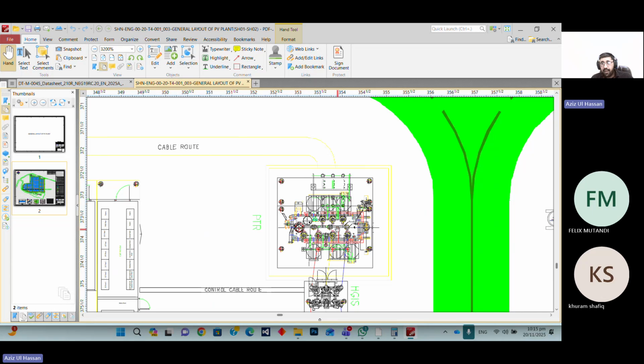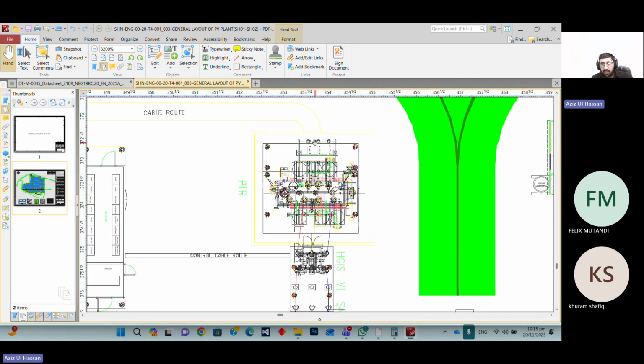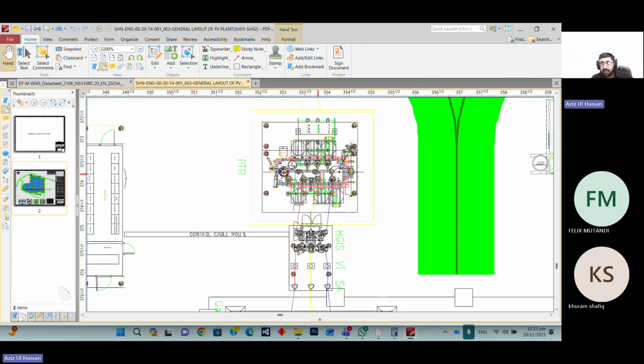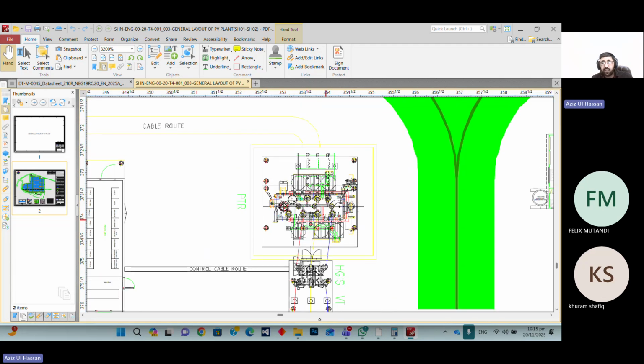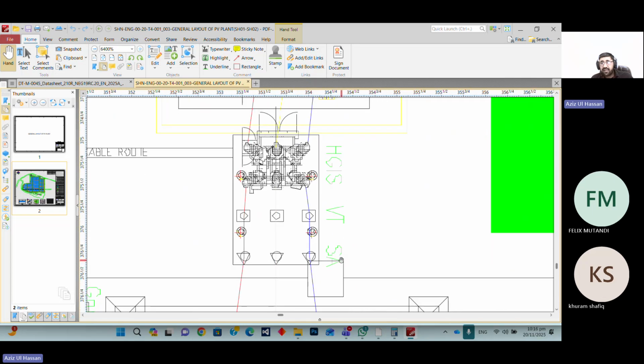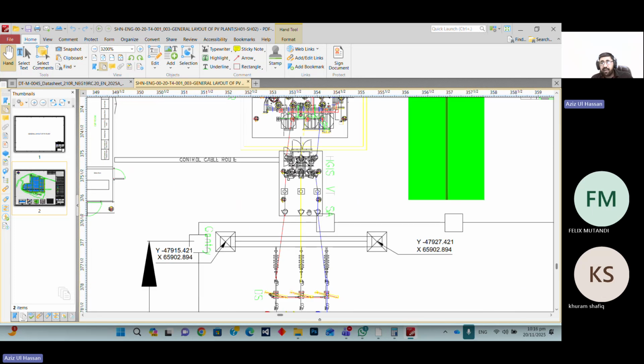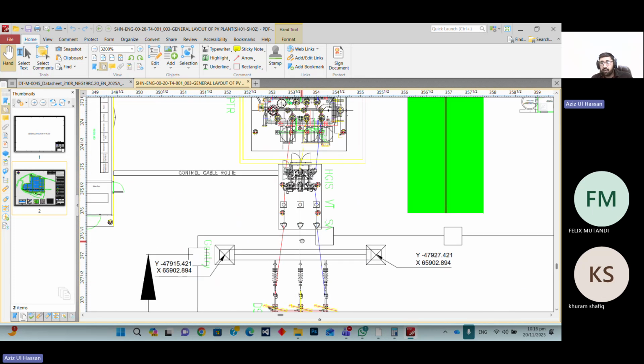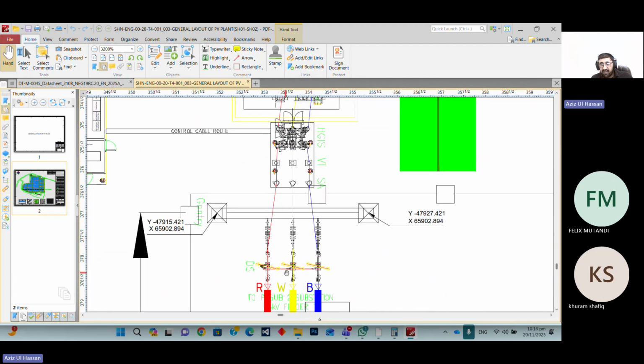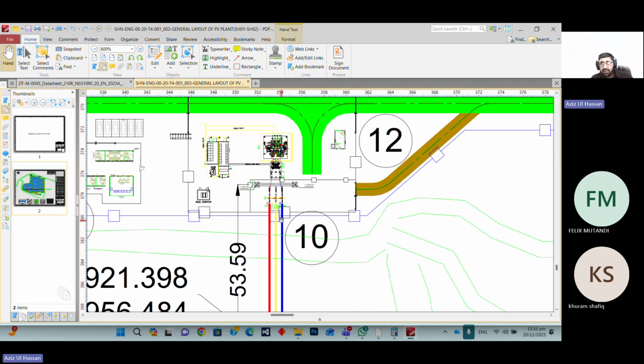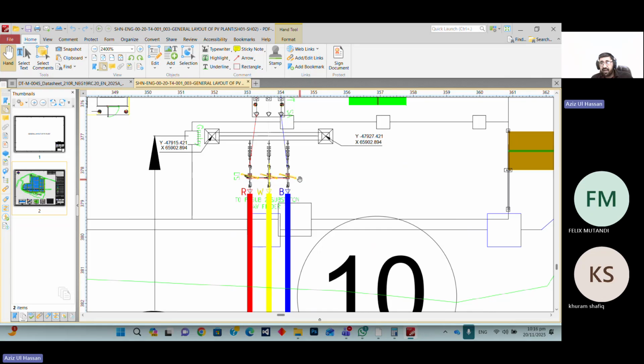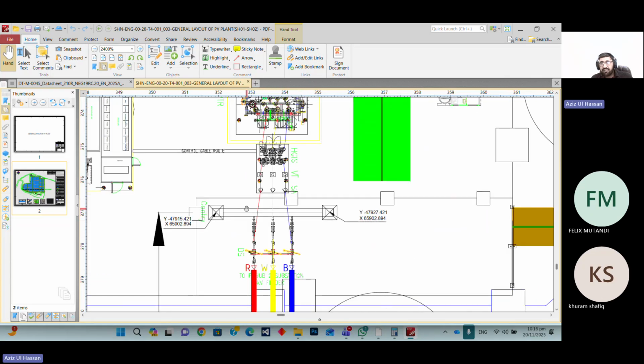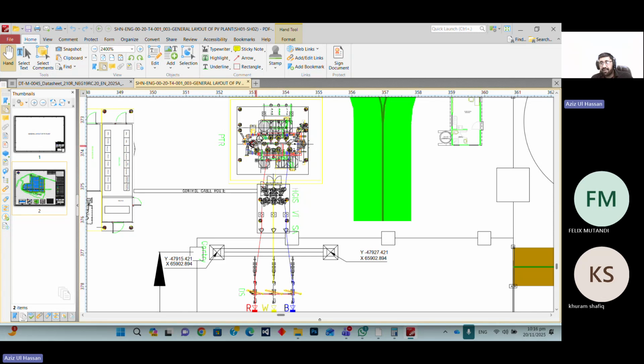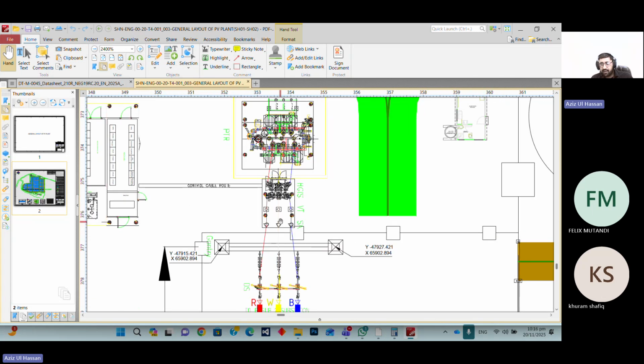You can see the cable tray there, and you have seen the cable inputs. They step up the power voltage from 33 to 66 kV, and we have a high voltage switchgear option there. We are giving our connection point in that room. So basically the client gives us the transmission line connection point in our PV area, inside the boundary gantry. These are the gantry options available, and we connect in that room our main transformer and the client's input cable, the transmission lines.